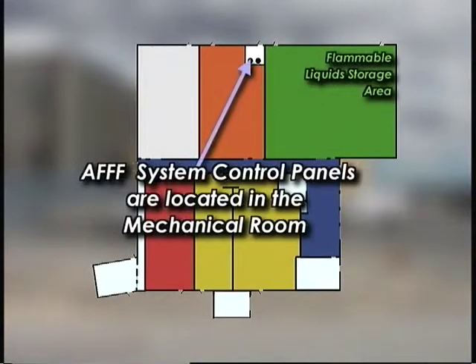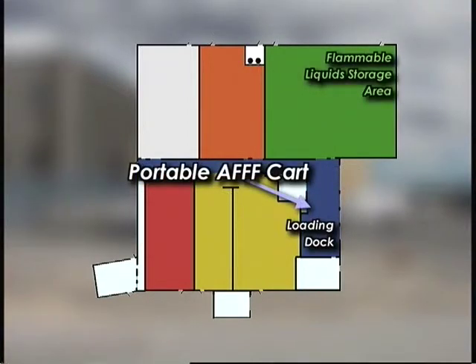The control panels for the AFFF equipment are located in the mechanical room, where the AFFF tanks and valves are located. This permits access for maintenance and operation of the panel without entering the spaces served. This is designed to minimize risk to responding emergency personnel if the system must be accessed for information or reset during an emergency. A portable AFFF system is located in the loading dock area.